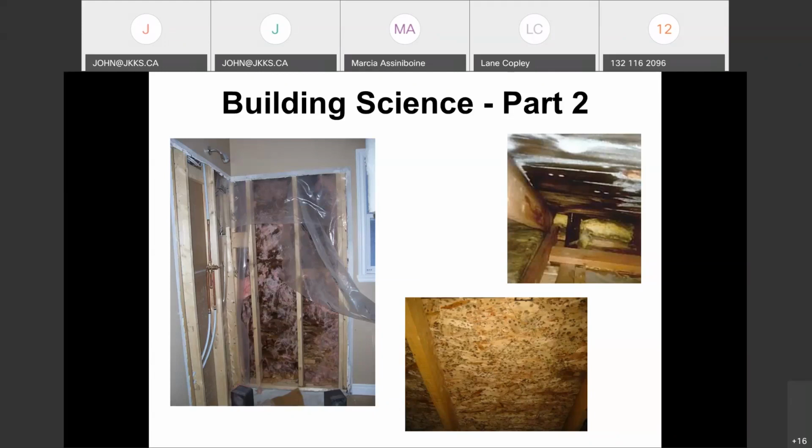Okay. And we can see here the signs of the wet fiberglass insulation still, to some degree, adhering to the wet back of the exterior sheathing. So again, here's evidence of, I guess it could be either moisture coming through the sheathing itself or the dew point, because of temperature difference, occurring inside that wall.